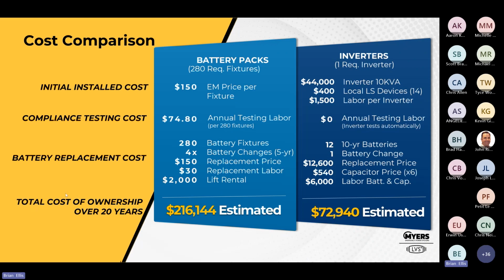So this is ownership over 20 years. So if we're using the 280 battery packs at 10 watt, and this is contractor net, by the way, guys, so I put like 30 points on this. So think about 280 fixtures, $150 per, annual testing and labor. But then you got to buy this battery pack 3 more times if it's only 5 years for a battery pack and we want a 20-year lifetime. So we're looking at $200,000 over the life of the system, the 20-year life.